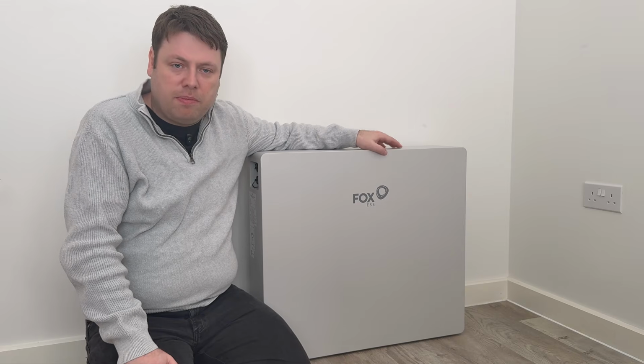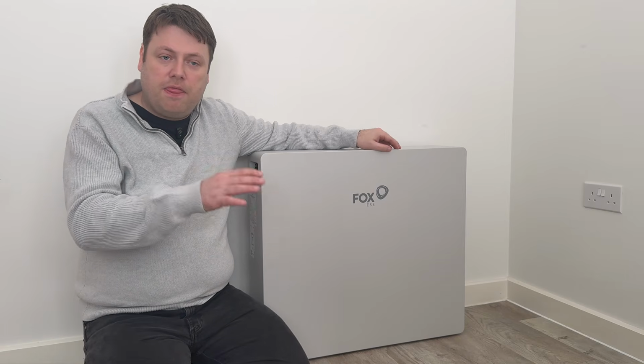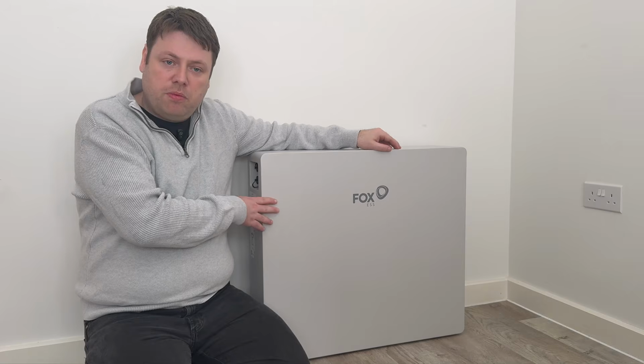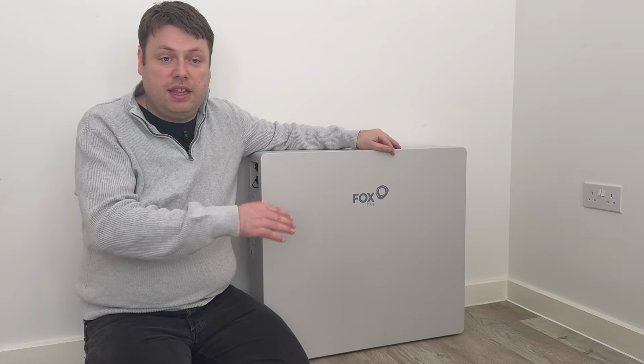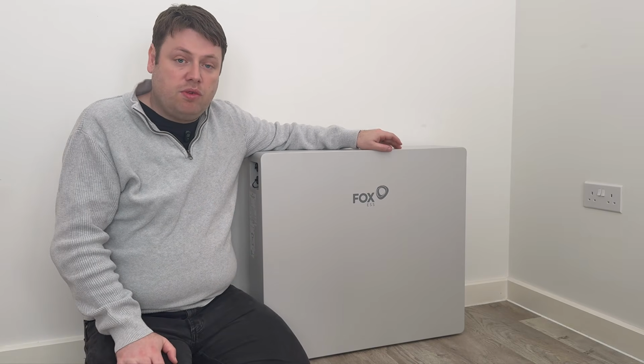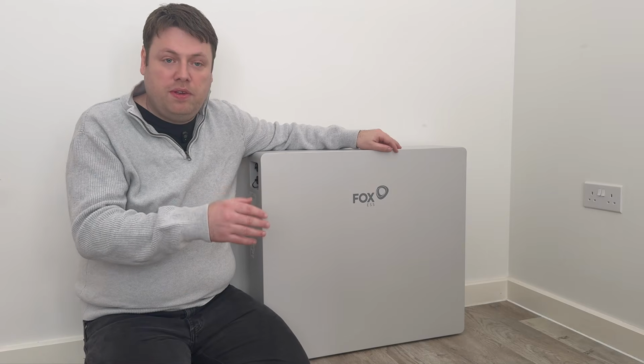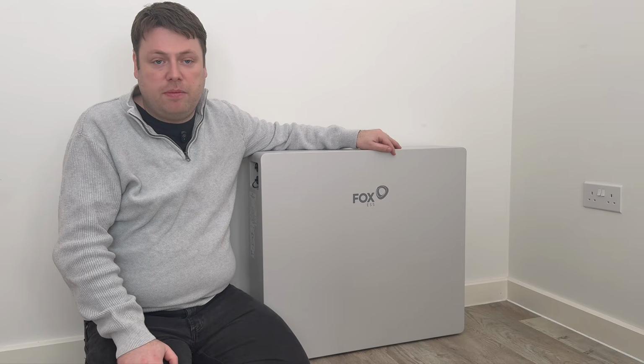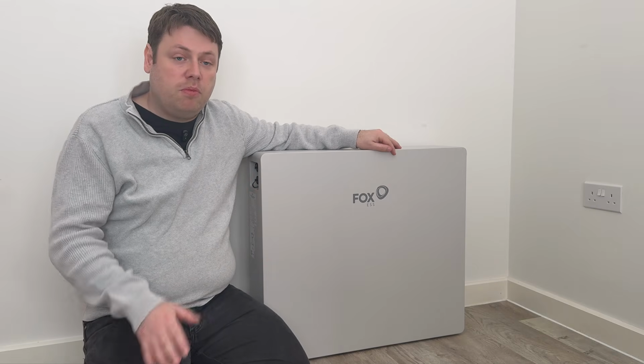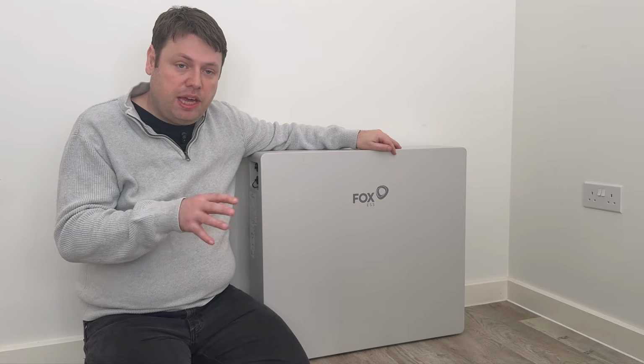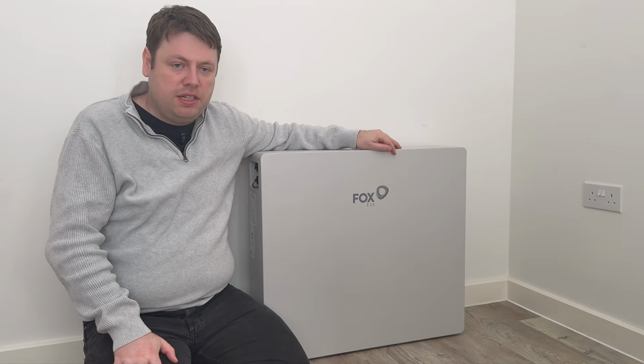But the fact that these are backwards compatible with the previous generation is really important for existing customers that have made an investment in their battery system, and they may want to scale it a year or two after its initial installation and find that that model they had installed is no longer available, but this one is compatible. And it's the same for the EQ range. So Fox released the EQ range of batteries to replace what was called the ECS, or the cubes. Those EQ batteries also have a compatibility matrix, so you can often add the latest model with the older models as well, as long as you keep the same battery type, the same battery voltage, etc.